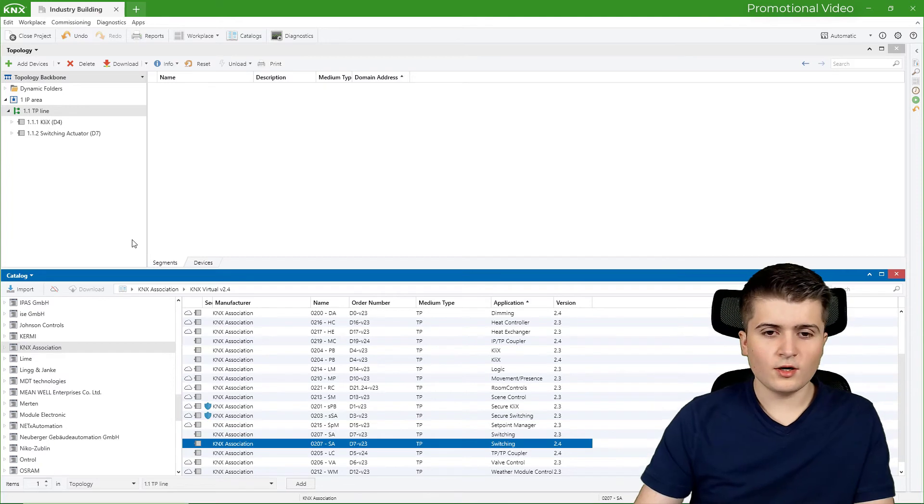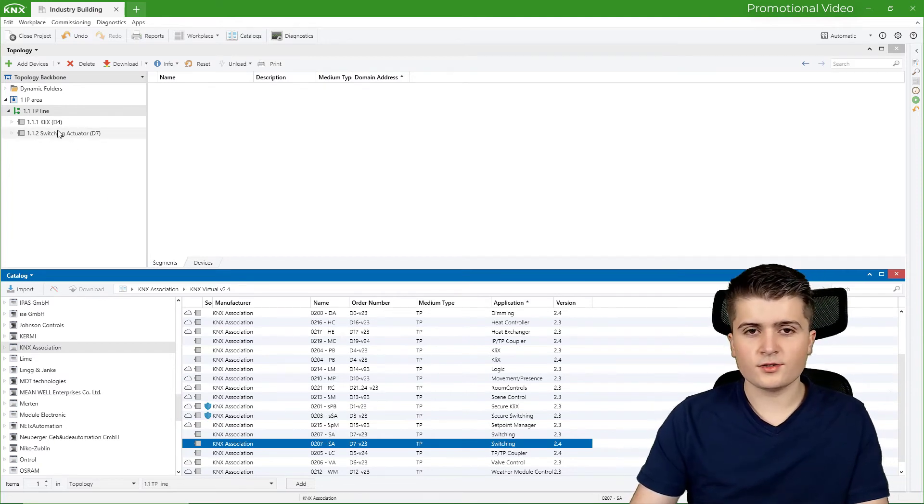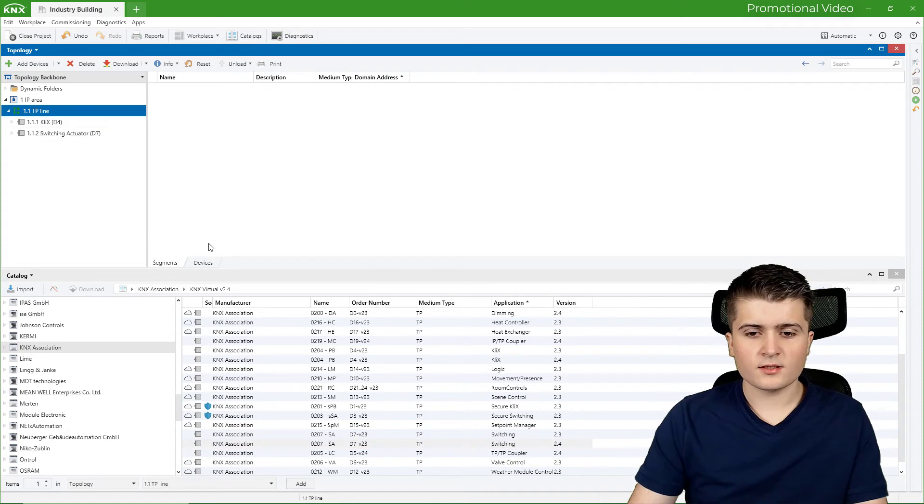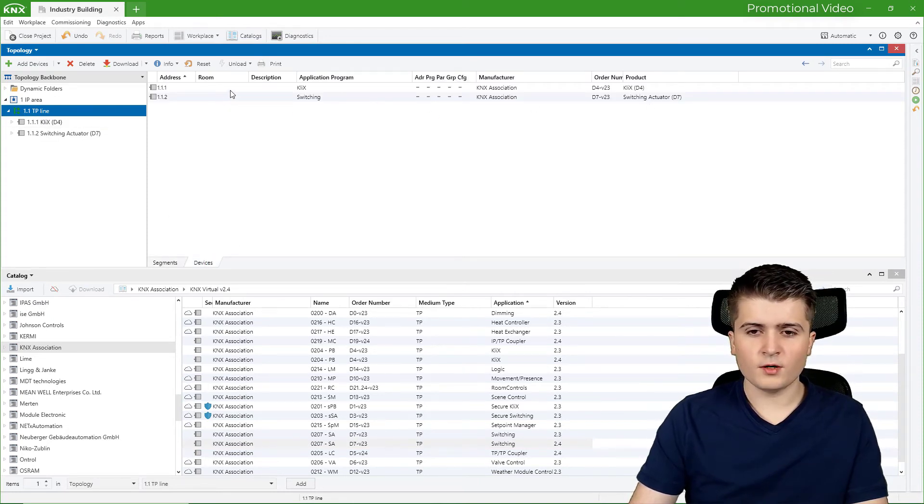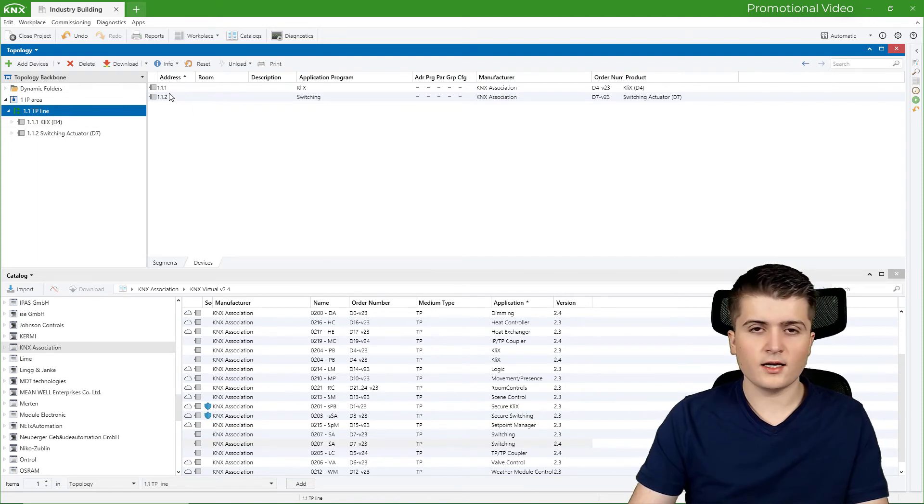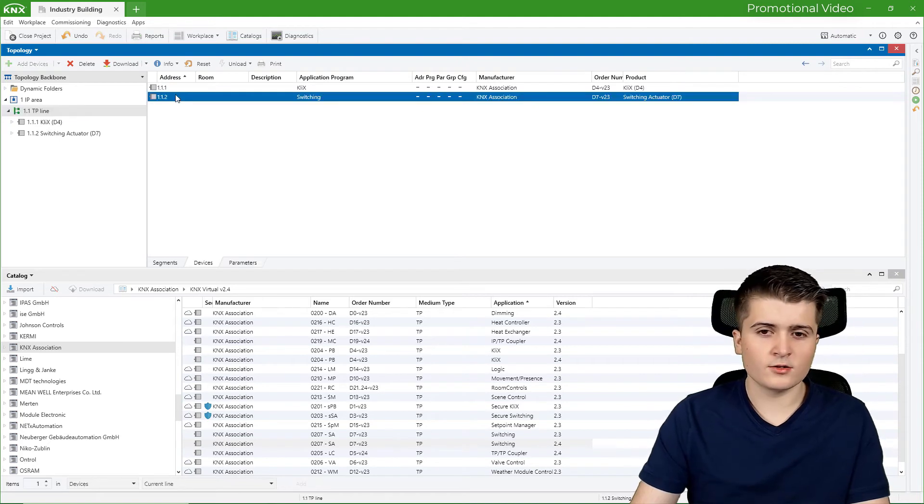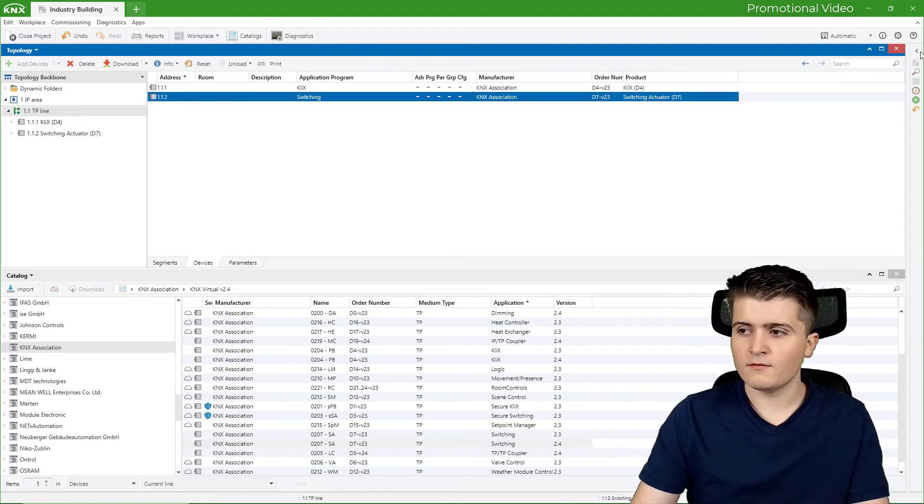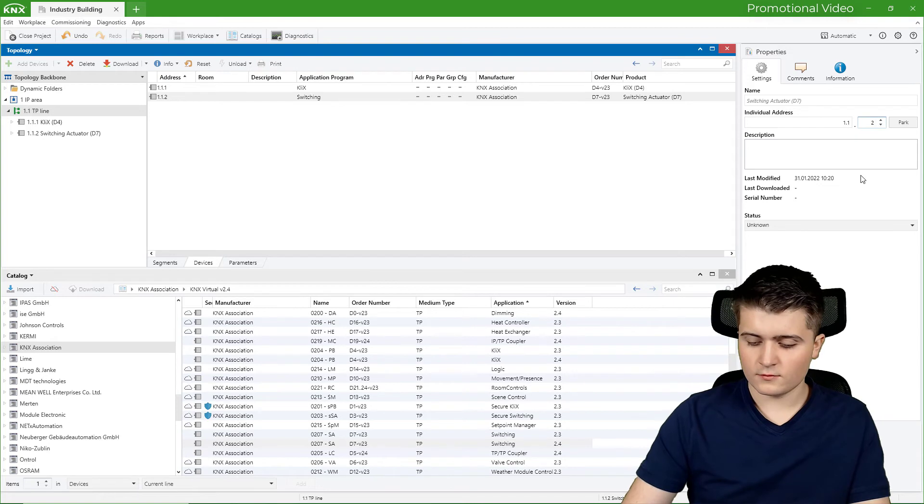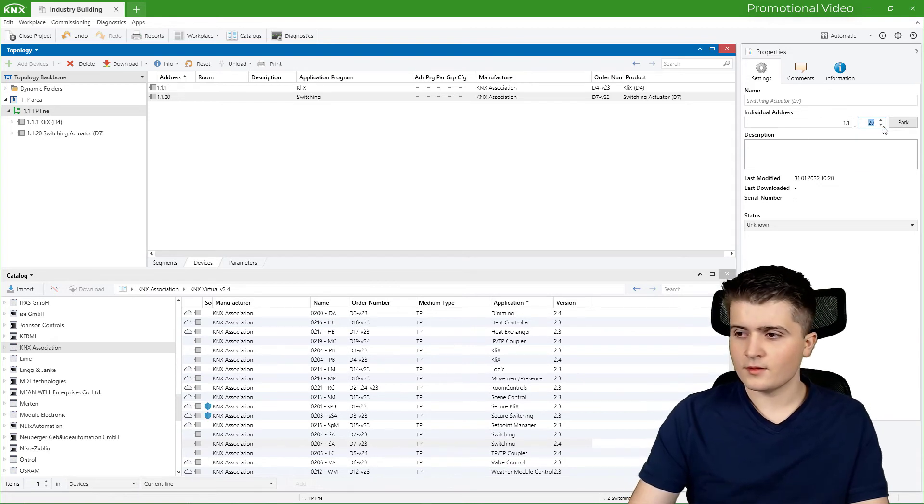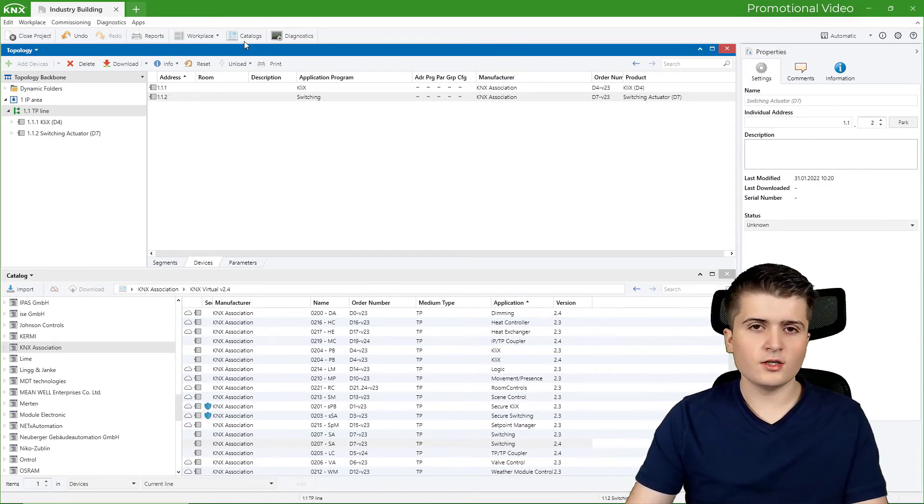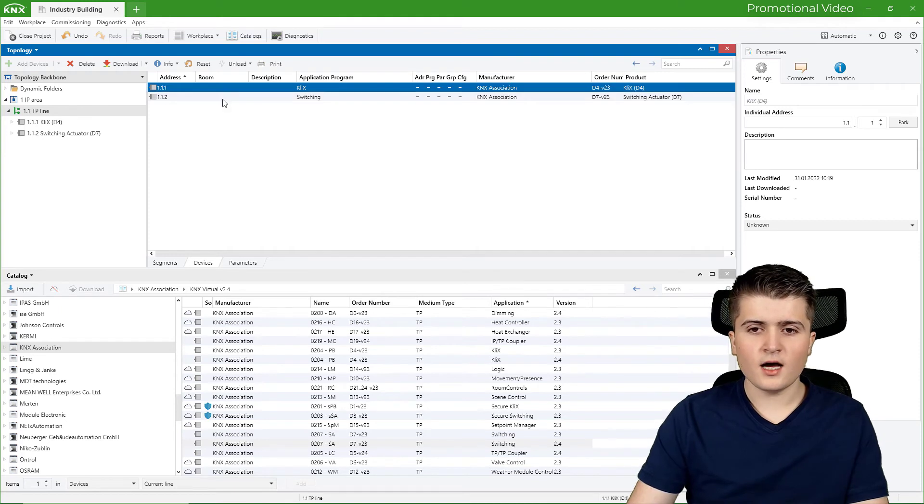So now also the switching actuator is added to the twisted pair line. And when we take a look at the twisted pair line, and I go here to devices, we can see that both devices are associated to the line. So they get their physical address 1.1.1 and 1.1.2. And I can also change it by opening up this properties page here, for example 20. And we will go back to 2. But we can also see that those devices aren't associated to any room for now.